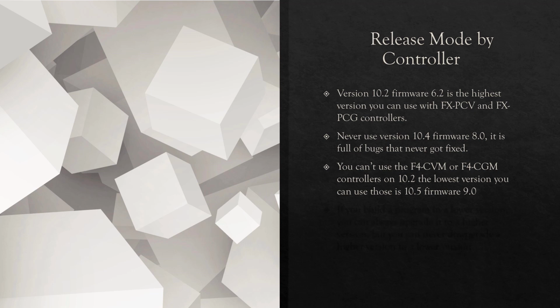You can't use the new controllers at 10.2. So obviously, if you're doing a job that has both, you're going to program the lower controllers at 10.2, switch your version to 10.5, or right now 10.6 is out, and load the newer stuff at 10.6.